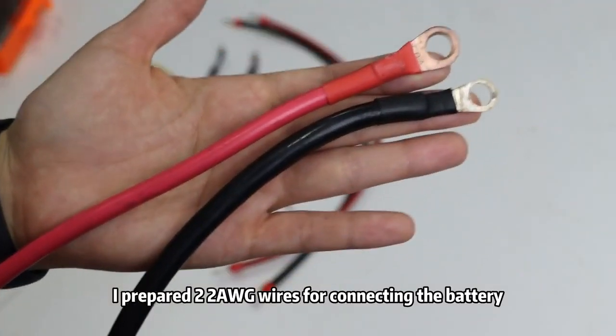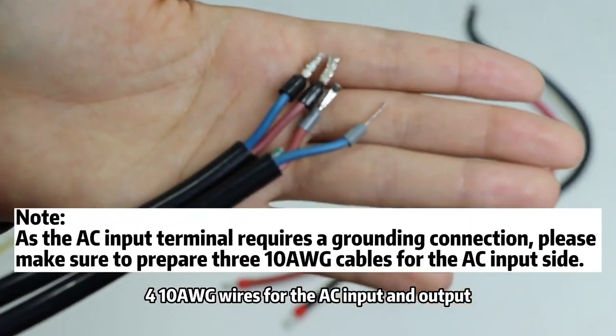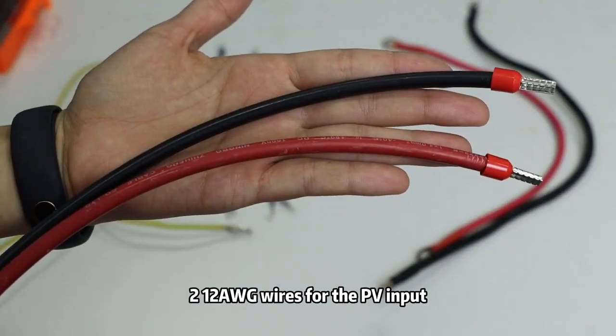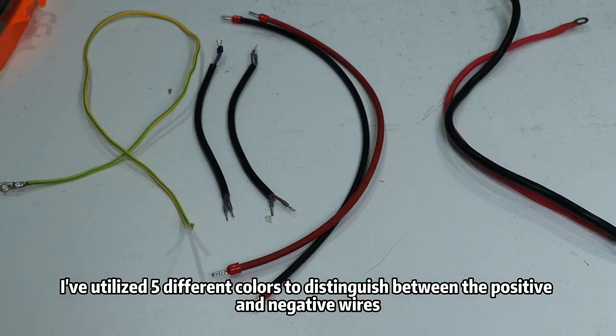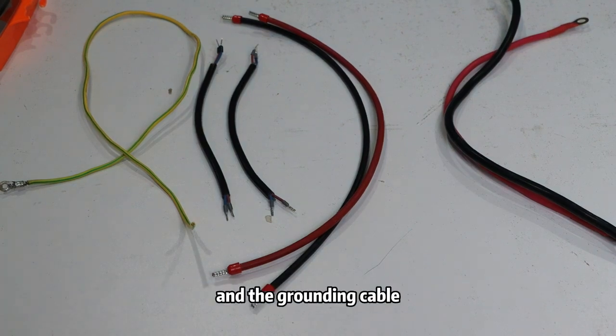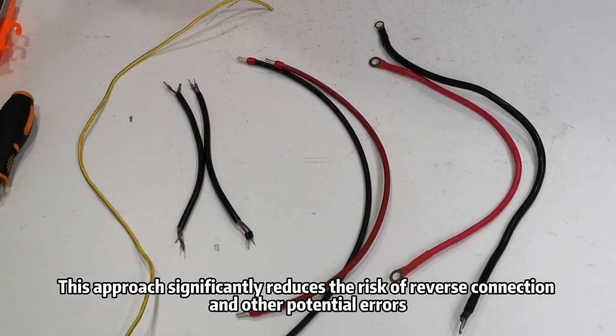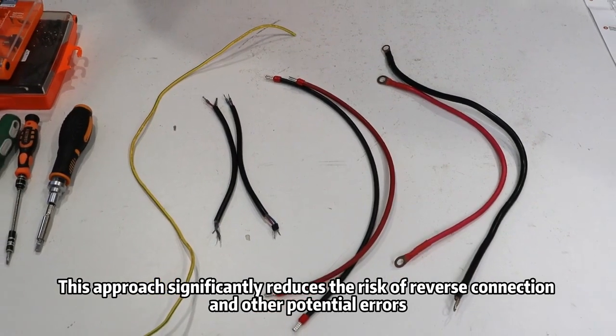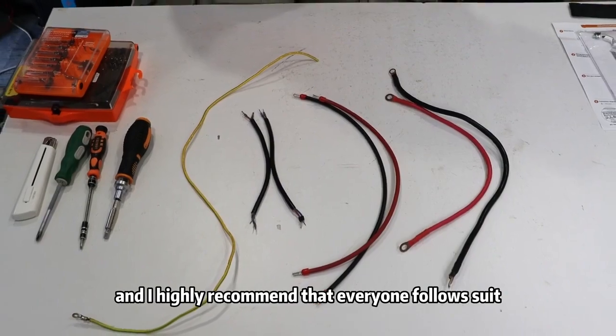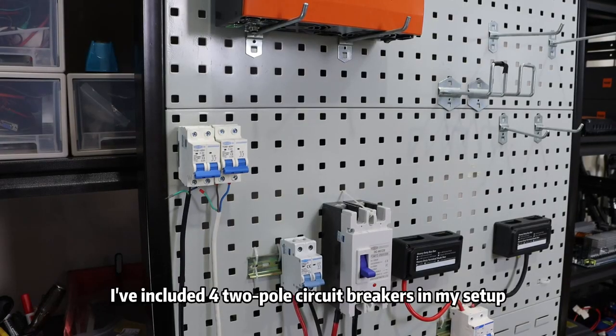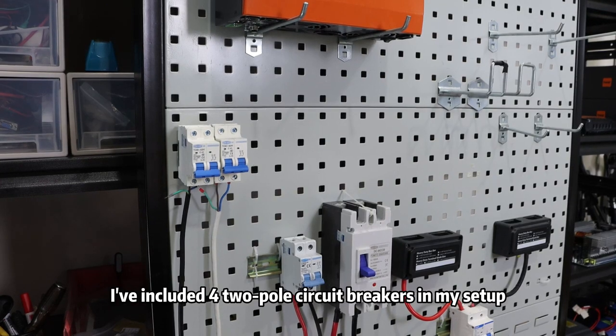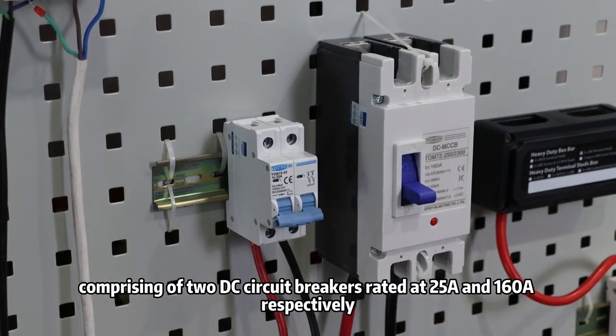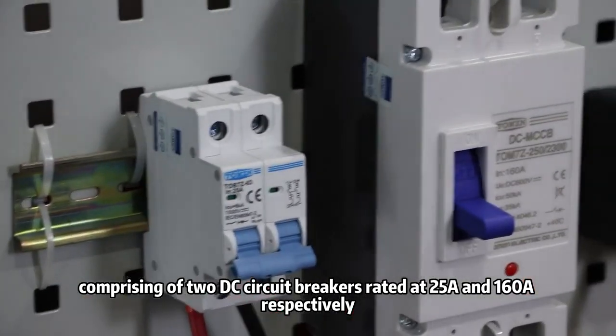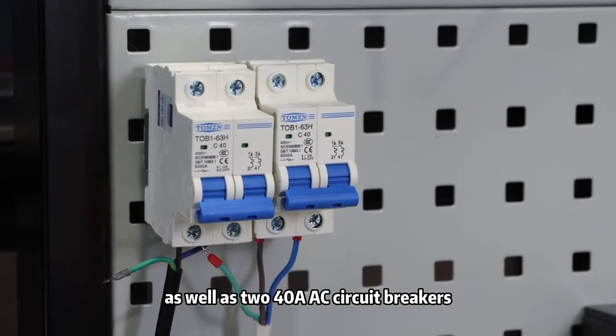Therefore, I prepared 2 2-gauge wires for connecting the battery, 4 10-gauge wires for the AC input and output, 2 12-gauge wires for the PV input, and 1 11-gauge wire for grounding the device. Here I have utilized 5 different colors to distinguish between the positive and negative wire, the live wire, the neutral wire, and the grounding cable. This approach significantly reduces the risk of reverse connection and other potential errors, and I highly recommend that everyone follow suit. Additionally, I have included 4 2-pole circuit breakers in my setup, comprising 2 DC circuit breakers rated at 25 ampere and 160 ampere respectively, as well as 2 40 ampere AC circuit breakers.